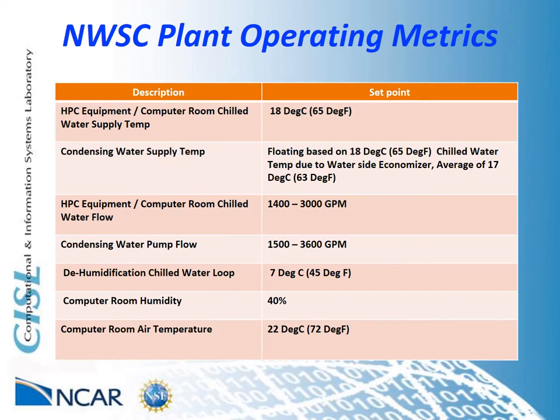Out of the design process, the following metrics for the NWSC were created. The HPC chilled water would be provided at 18 degrees Celsius with a chilled water flow potential of up to 3,000 gallons per minute. The computer room would also maintain 40% humidity, and the room air temperature would be controlled to 22 degrees Celsius. These metrics developed were based on providing an efficient cooling system that would be extremely versatile and allow for future expansion.